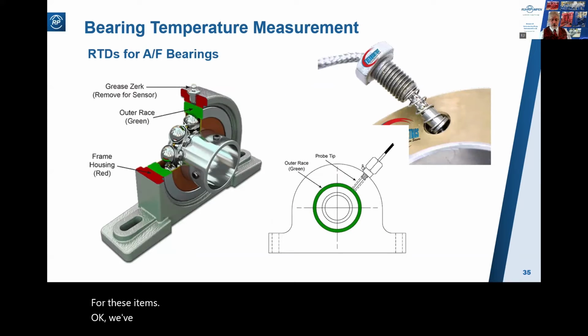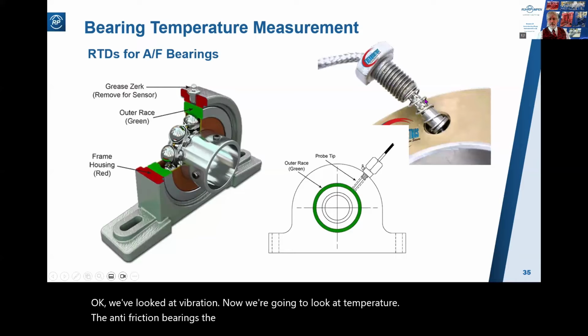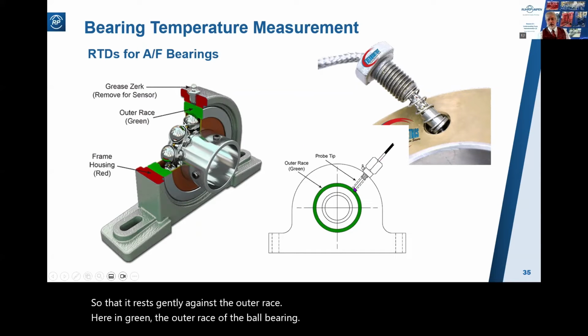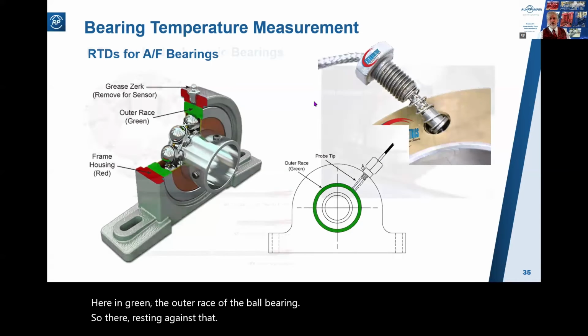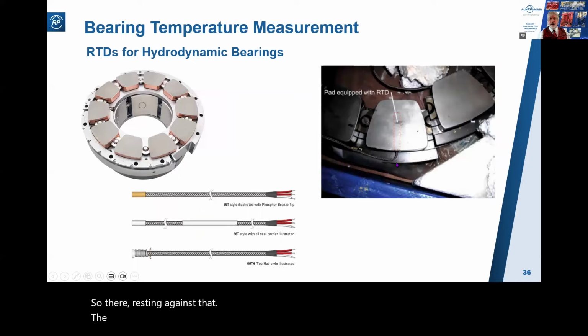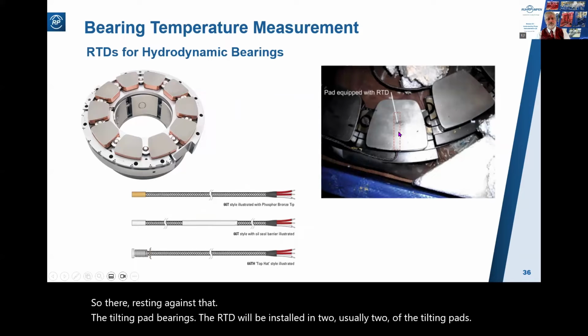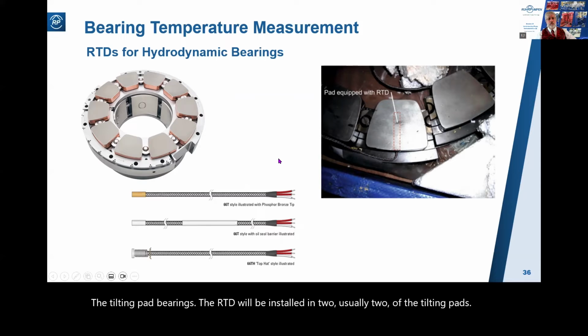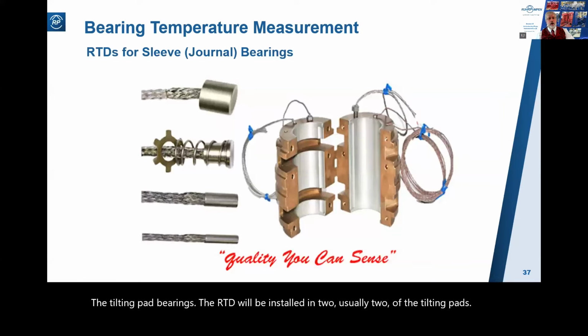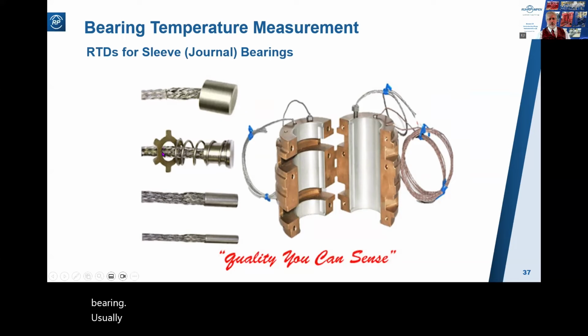Okay, we've looked at vibration. Now we're going to look at temperature. For anti-friction bearings, the RTD will be spring mounted so that it rests gently against the outer race, here in green, the outer race of the ball bearing. So there, resting against that. For tilting pad bearings, the RTD will be installed in usually two of the tilting pads. And for journal bearings, sleeve bearings, again, it's embedded in the metal of the bearing. Usually this type spring-loaded and with a spring clip there to hold it in place.